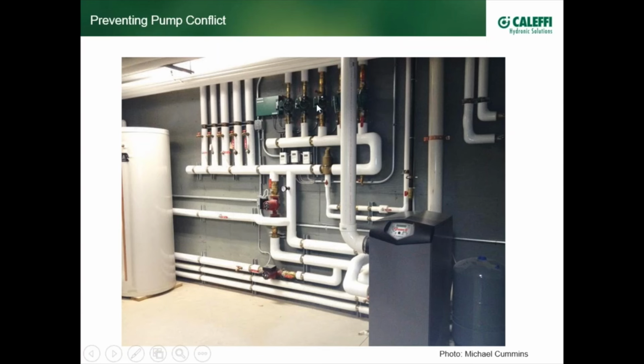If it were allowed to, it would reduce the flow rate in the circuits those pumps are driving. They would be coupled. We want to decouple them. In fact, designers sometimes will refer to devices for hydraulic separation as decouplers. Now, this job uses one form of decoupling that's been around for a long time, and that's taking two T's, spacing them closely together, a very effective form of creating hydraulic separation, or primary secondary, if you will.